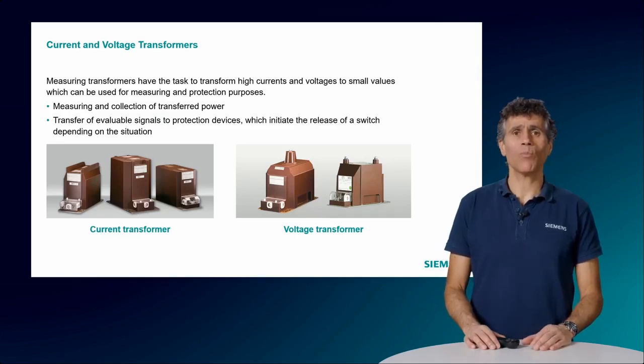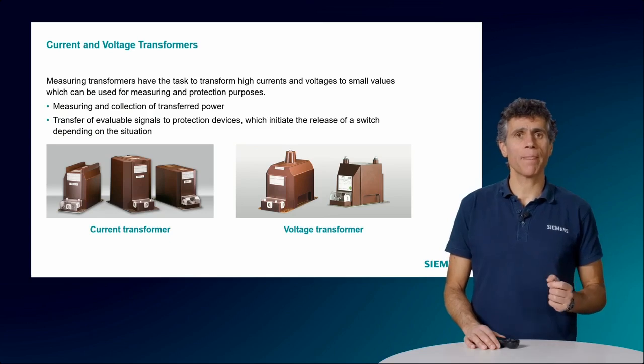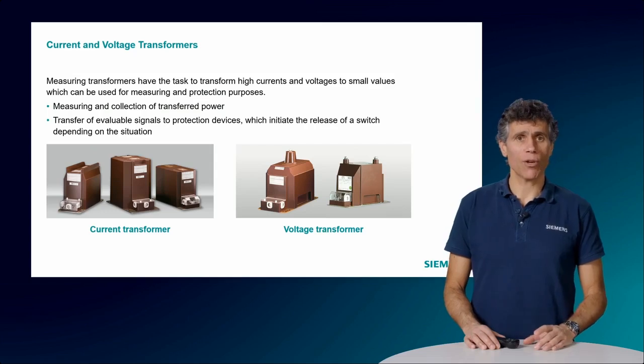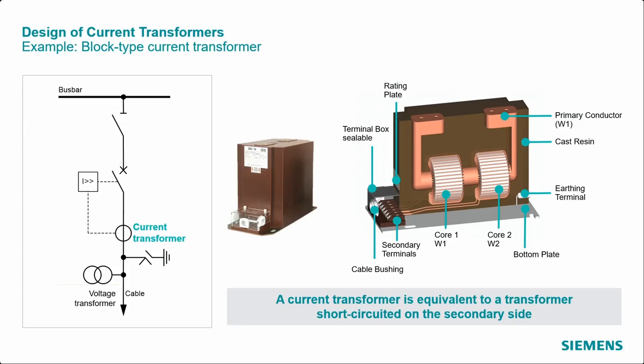The most common ones are the block-type transformers. You will probably remember them from the cutout drawing of a panel that we saw in the beginning. Let's start with those, and after I will show you also the more modern so-called low-power instrument transformers. Here is a block current transformer, shortly called CT, standing for current transformer. The current flows through the primary conductor. Usually 3 CTs are used in one panel, one per phase, depending on the protection functions required. The CT is connected to the line carrying the high current that needs to be measured or monitored.